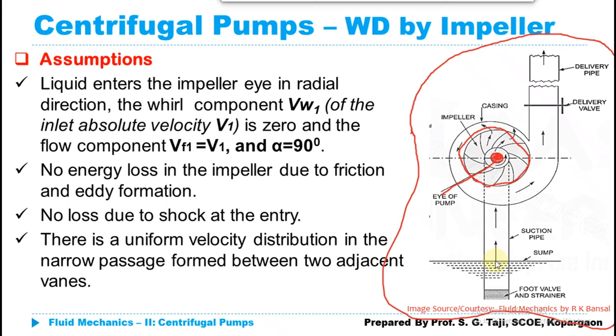When the impeller starts rotating, there will be development of suction at the eye, and due to this suction, water will be drawn from the source or sump of water to the eye of the impeller. The water will then start to rotate along with the backward curved vanes of the impeller. As the water rotates, centrifugal force develops and pushes it outward, away from the central axis.